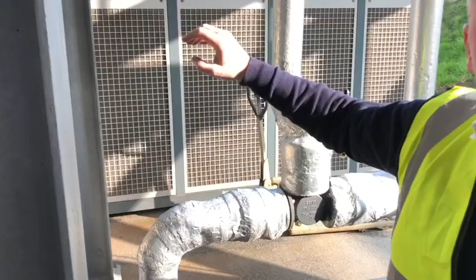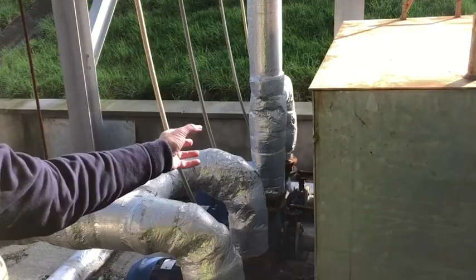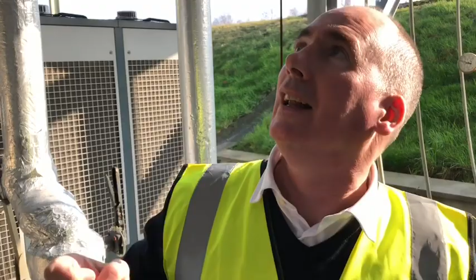That basically comes back down, up there, back down here, and on down then through the two chillers which are connected in parallel. We're then coming back off the chillers into the cold side of the tank, and we have a secondary loop with our secondary pumps pumping back into the factory. So very simple, very straightforward, but we can design this in a way that we can give much more free cooling than with a chiller with an integral free cooling coil.